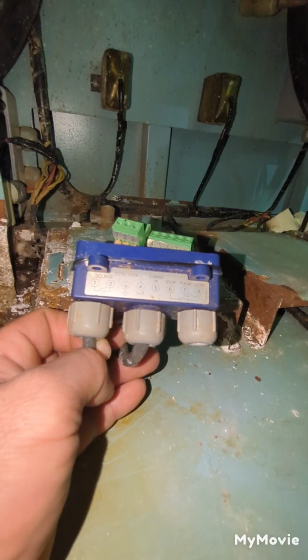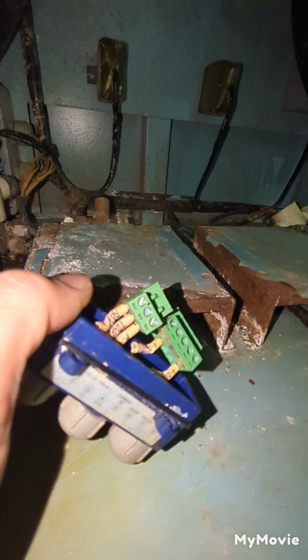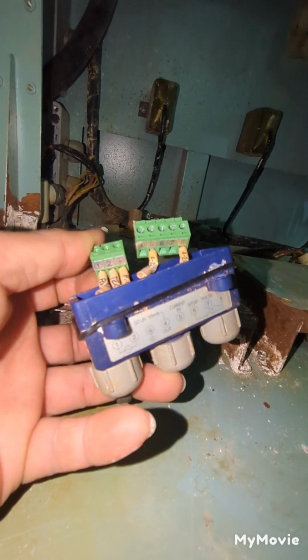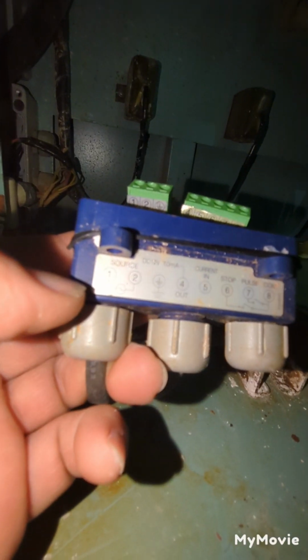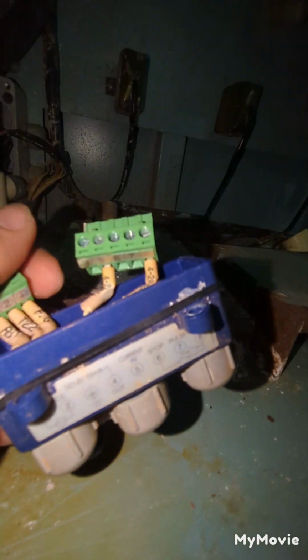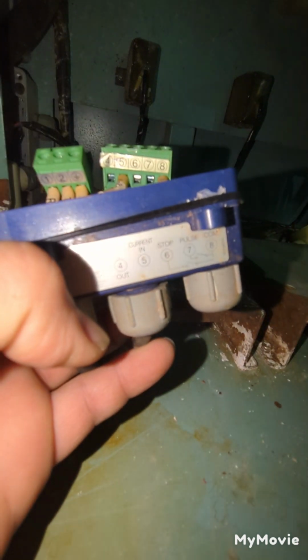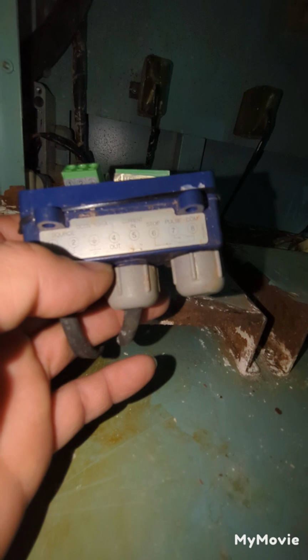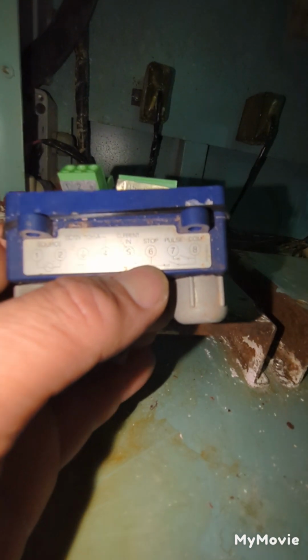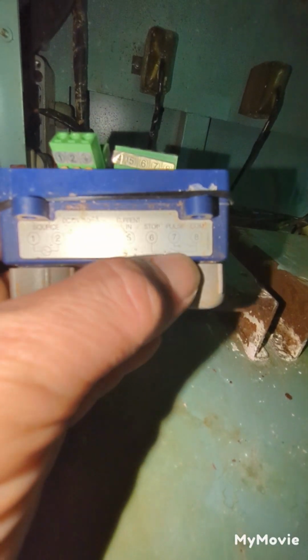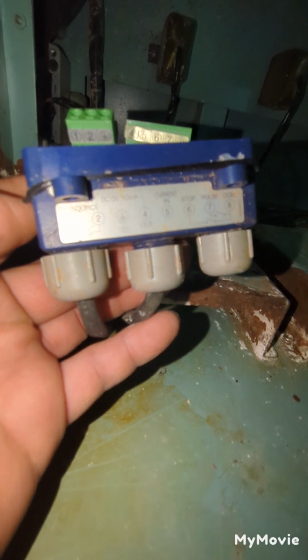Let's check the solenoid. So here is the wiring diagram of my motor. Terminal 1 and 2 is 230 volts, as you can see here. Then on terminal 5 and 8, there is 4 to 20 milliampere plus and minus. So 5 is current positive, and 8 is the common. Also, 6 is the stop switch, and 7 is the pulse switch.